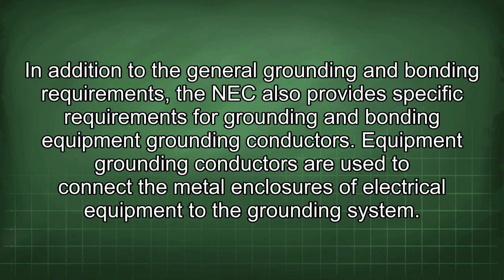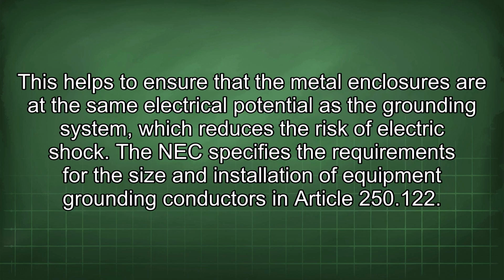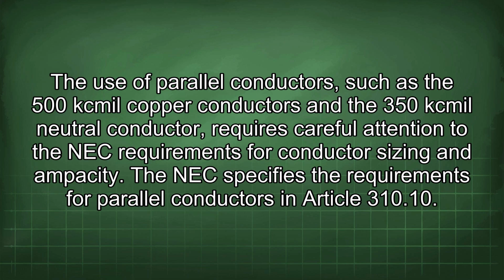equipment grounding conductors. Equipment grounding conductors are used to connect the metal enclosures of electrical equipment to the grounding system. This helps to ensure that the metal enclosures are at the same electrical potential as the grounding system, which reduces the risk of electric shock. The NEC specifies the requirements for the size and installation of equipment grounding conductors in Article 250.122.